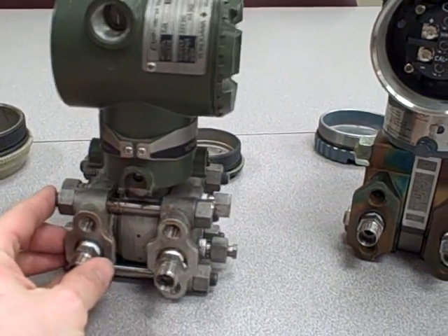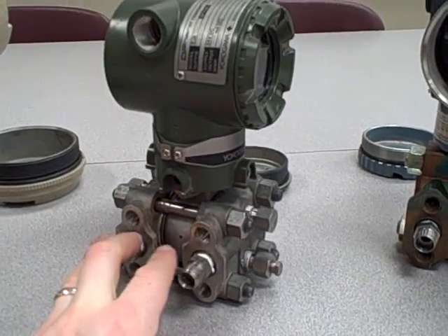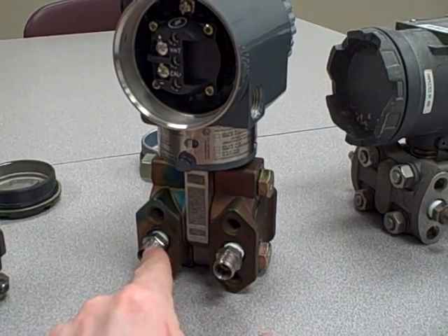And they all use different sensing technologies as well. Some of these use differential capacitance, such as the Rosemount over here. Some use a resonant element, such as the Yokogawa unit. Others use a piezo-resistive technology, such as the Foxboro. But they all do the same thing — they measure a difference of pressure between the two inputs.